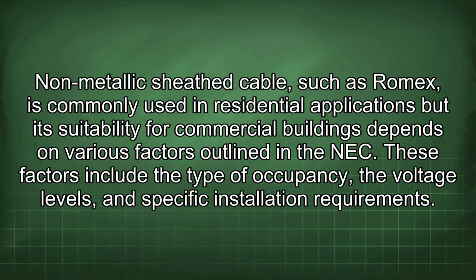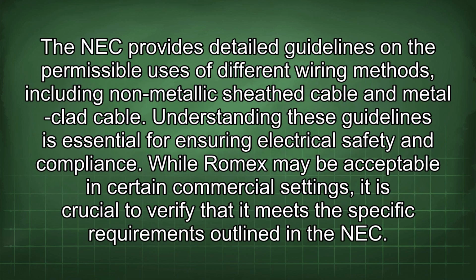Non-metallic sheath cable, such as Romex, is commonly used in residential applications, but its suitability for commercial buildings depends on various factors outlined in the NEC. These factors include the type of occupancy, the voltage levels, and specific installation requirements. The NEC provides detailed guidelines on the permissible uses of different wiring methods, including non-metallic sheath cable and metal-clad cable. Understanding these guidelines is essential for ensuring electrical safety and compliance.